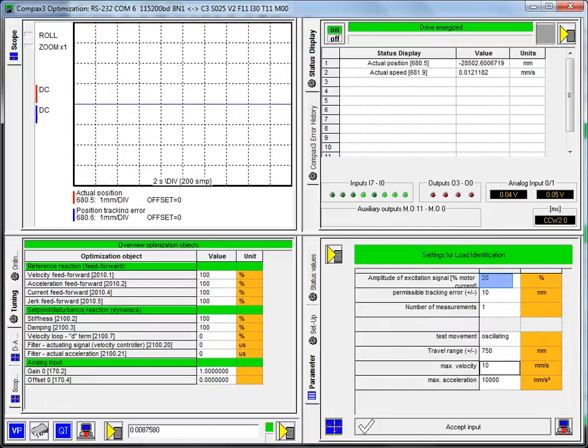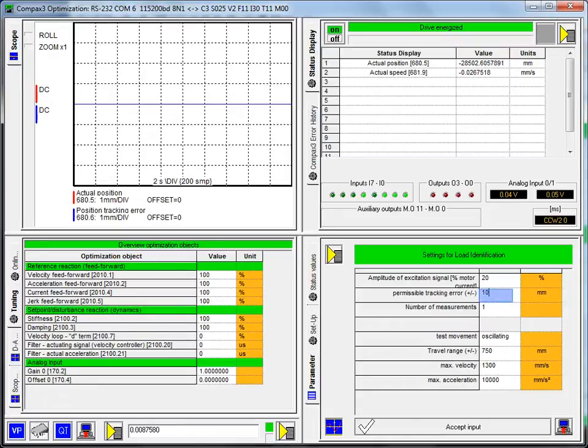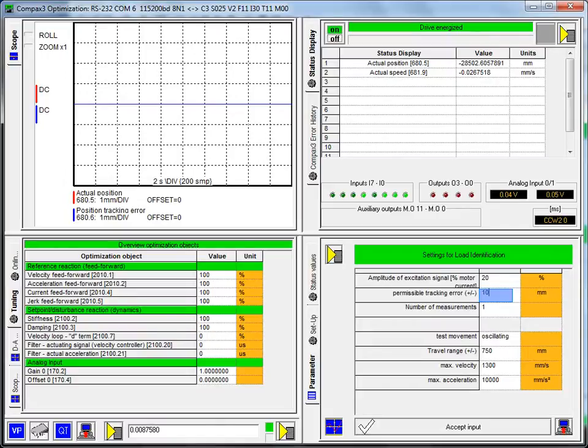The amplitude of the excitation signal is the percentage of the motor current that it will inject into the motor and shake the rotor, try to detect what the load is that's connected to the motor shaft. The default value is 20%. That's a good value in my experience. The permissible tracking error, my unit is set to 65 millimeters per revolution. So I'm going to set that to plus or minus 650.